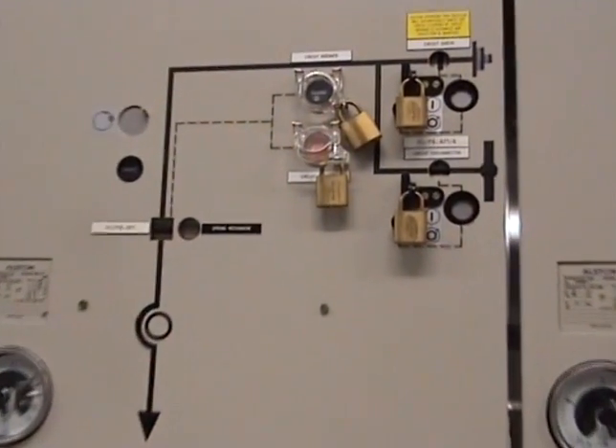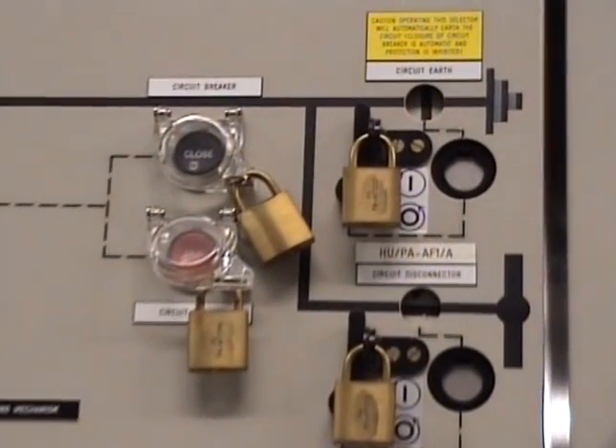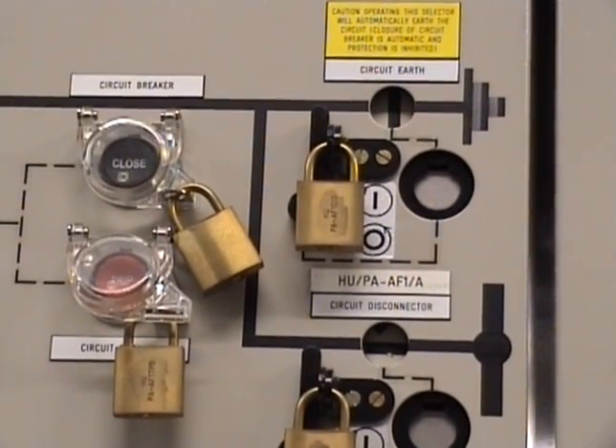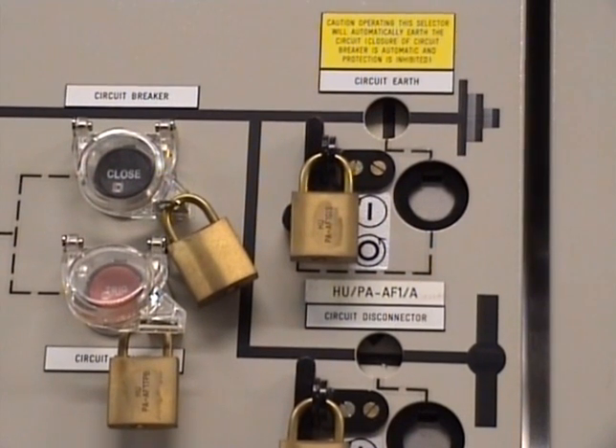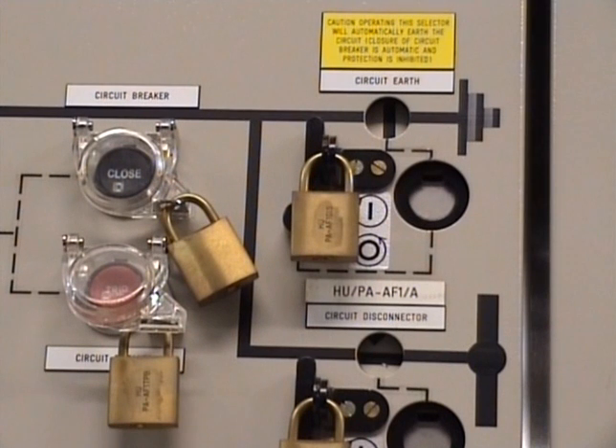Zooming in, we see in close-up the disconnector and the earth switch. This is in fact one switch which can be connected from the outgoing feed on the left to either the bus bar lower or the earth switch upper. In the lower it's feeding out via the circuit breaker to the equipment. In the upper it is connecting the equipment to earth.